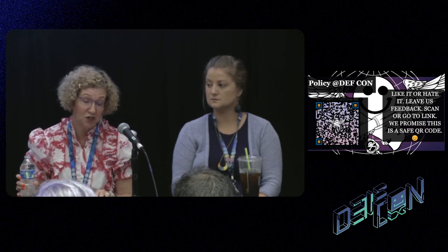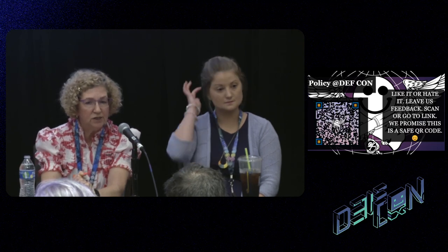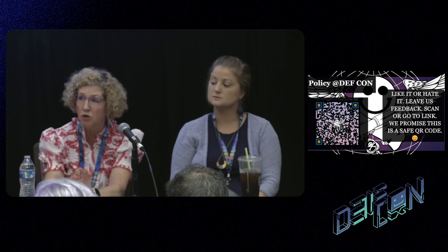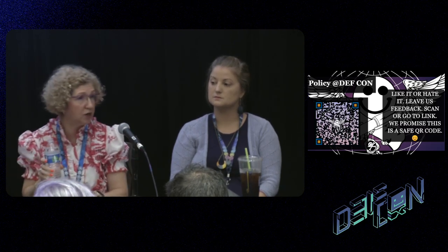At present, we also issued what's called a refuse-to-accept policy guidance on March 29th, which essentially states that as of October 1st of this year, if a submission comes into the agency that does not have the necessary elements for cybersecurity required for pre-market review, then that submission would get immediately rejected from going into the process of review, and it returns back to the sponsor, the manufacturer.